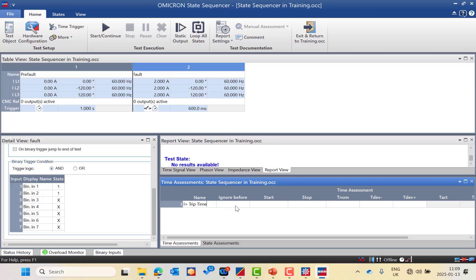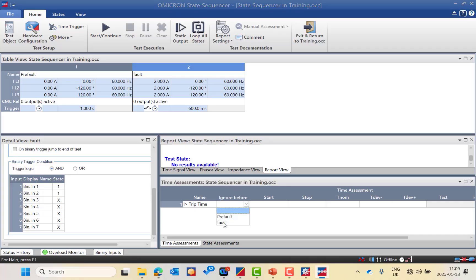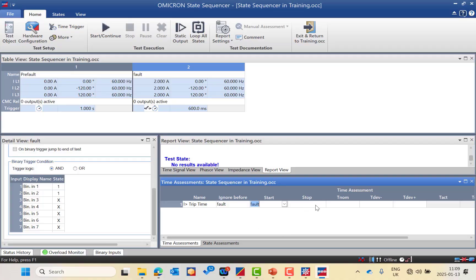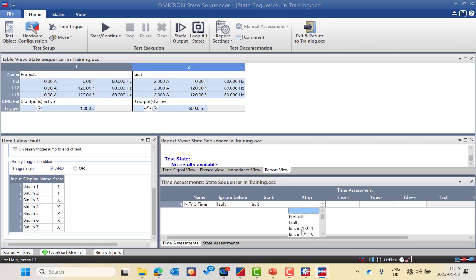I will add a time assessment and name it 'I greater trip time'. You can configure the 'ignore before' setting — I will start measuring the trip time from the beginning of state 2, because state 1 is pre-fault at zero amps and no tripping is expected. So I will ignore before state 2, which is the fault state. The start contact will be from the fault state, and the stop contact will be binary input 1 — the trip command changing from 0 to 1.